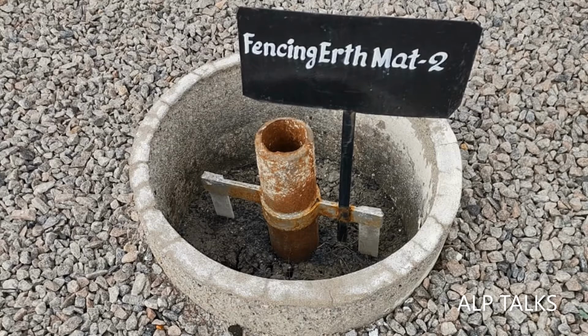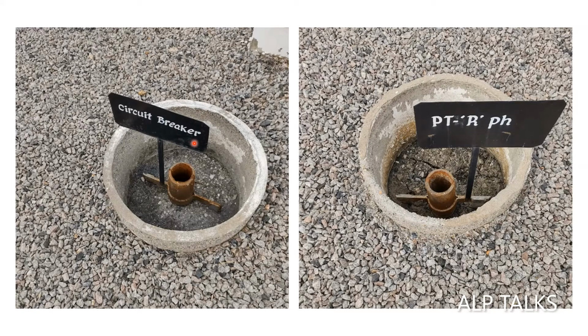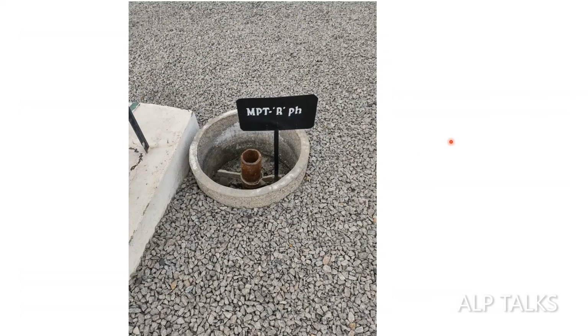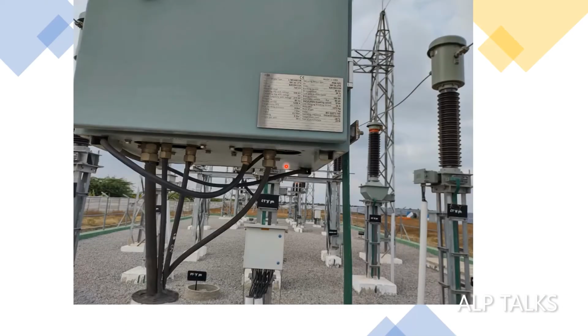This is the fencing earth mat. Generally they are doing chemical earthing, in this case pipe earthing, but with chemical they are doing the earthing arrangement. So for maintaining, this is circuit breaker earthing. This is the PT earthing or phase earthing. So yeah, it is a neatly maintained substation. We can see it in others also.